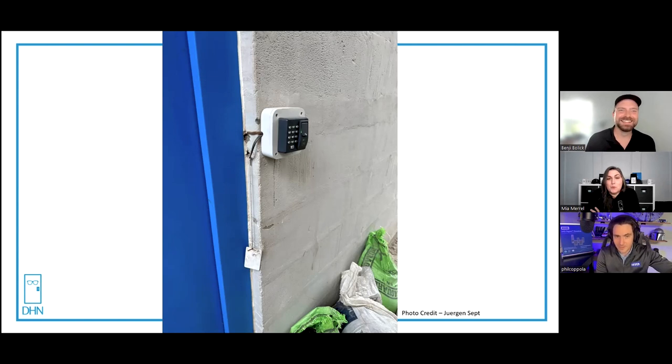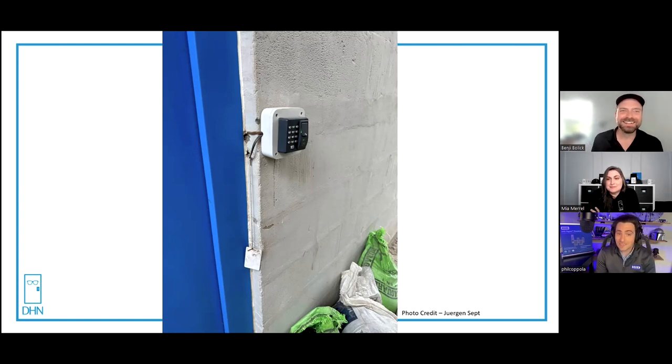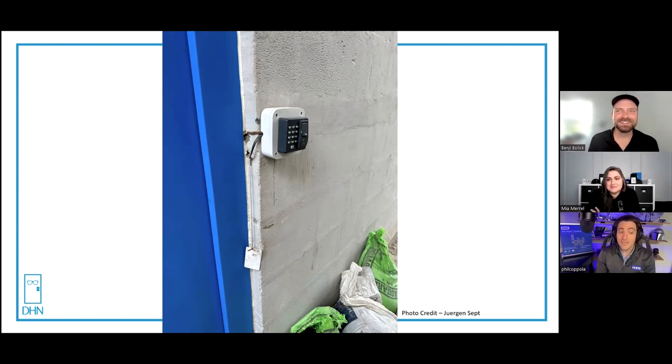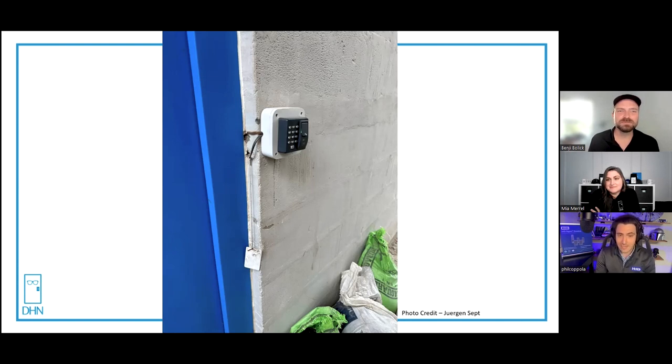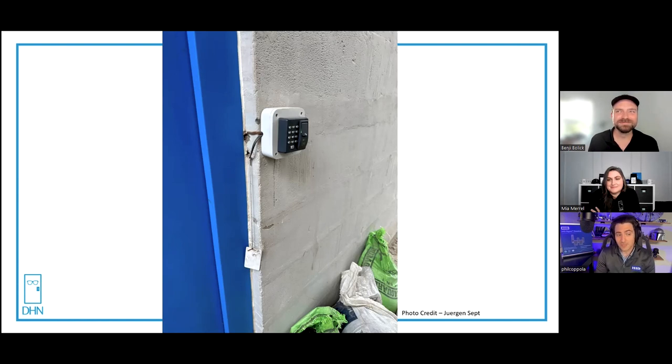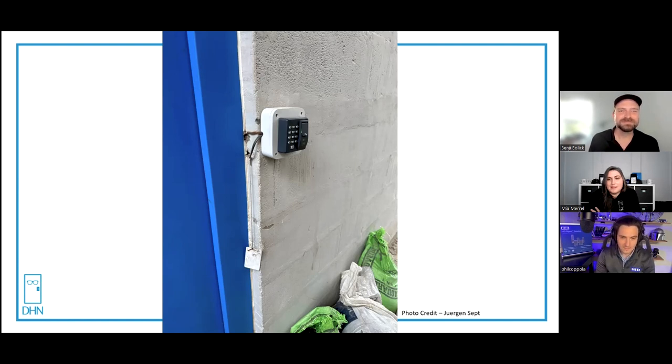Put some conduit there to hide the wires. On a scale of one to ten, from a life safety perspective, if that's a fail-secure door, that would be a 10—completely egregious. From a security perspective, that's pretty low.